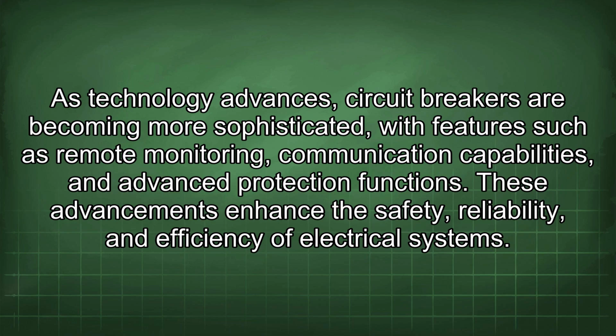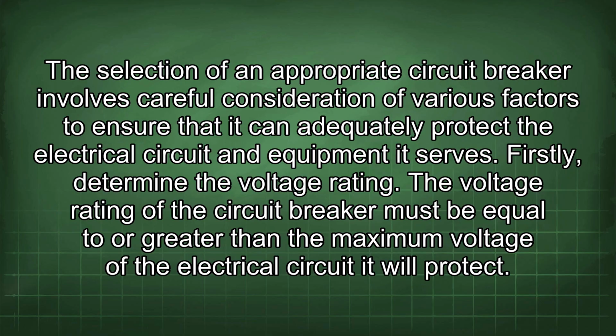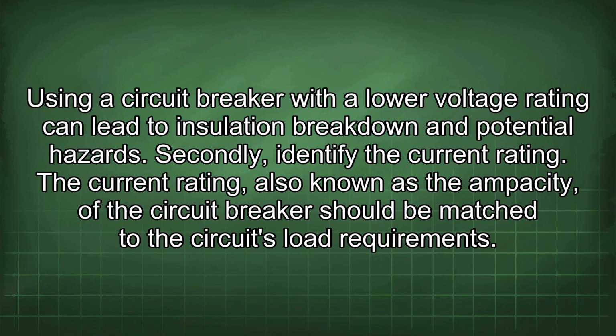These advancements enhance the safety, reliability, and efficiency of electrical systems. The selection of an appropriate circuit breaker involves careful consideration of various factors to ensure that it can adequately protect the electrical circuit and equipment it serves. Firstly, determine the voltage rating. The voltage rating of the circuit breaker must be equal to or greater than the maximum voltage of the electrical circuit it will protect. Using a circuit breaker with a lower voltage rating can lead to insulation breakdown and potential hazards. Secondly, identify the current rating.